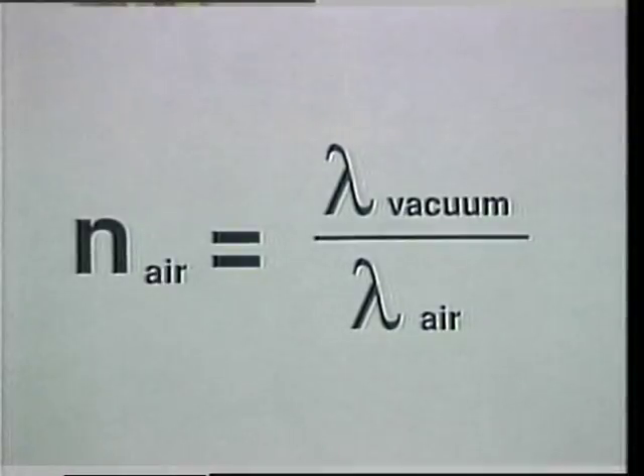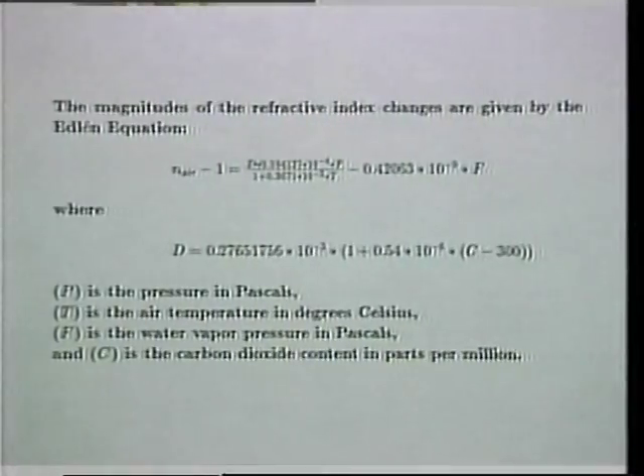Perhaps the biggest shortcoming of laser interferometers is their sensitivity to atmospheric changes: temperature, humidity, barometric pressure, and even carbon dioxide content. Variations in these environmental conditions cause changes in the refractive index of the air through which the beam travels. Changes in the refractive index result in uncompensated changes in the wavelength of the light. Variations in the standard with which you measure obviously undermines the validity of the measurement. Environmental errors can be quantified by determining the refractive index changes and calculating the resultant wavelength changes. The magnitudes of the refractive index changes are given by the Edlen equation.